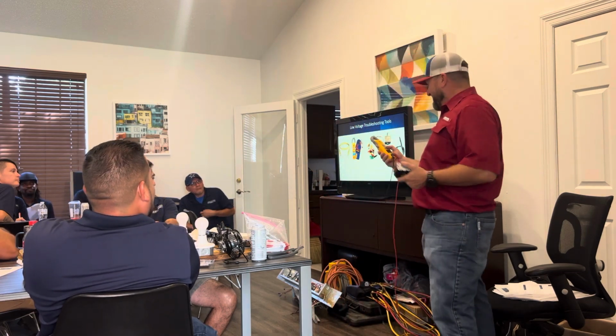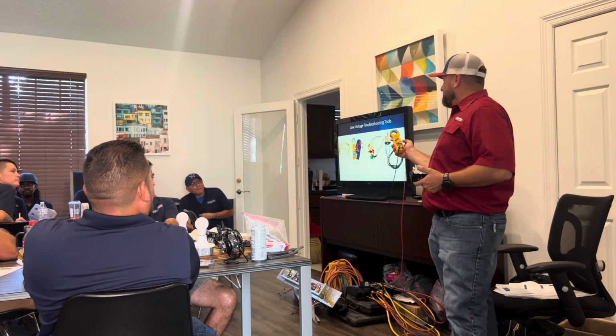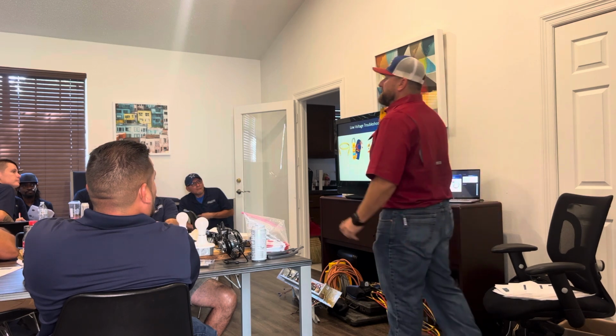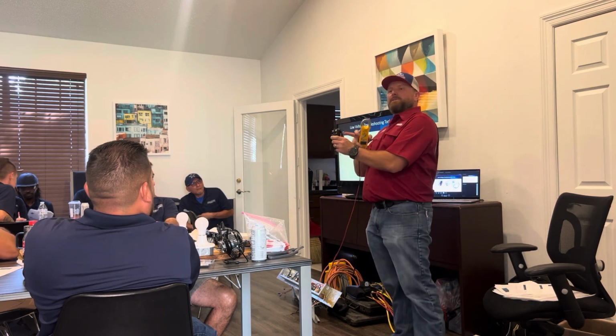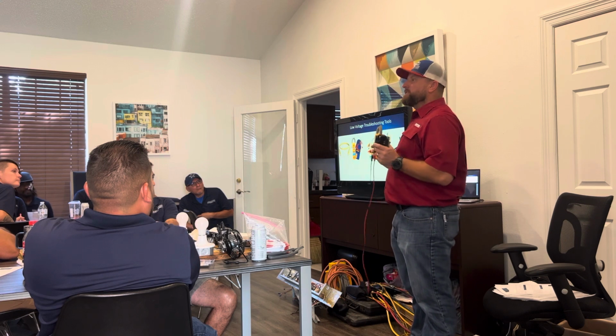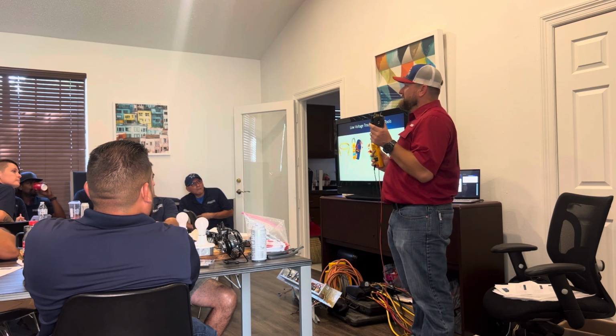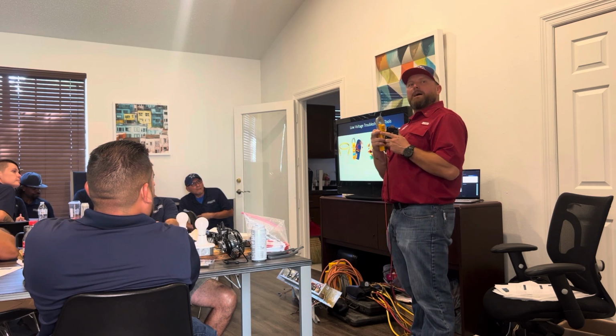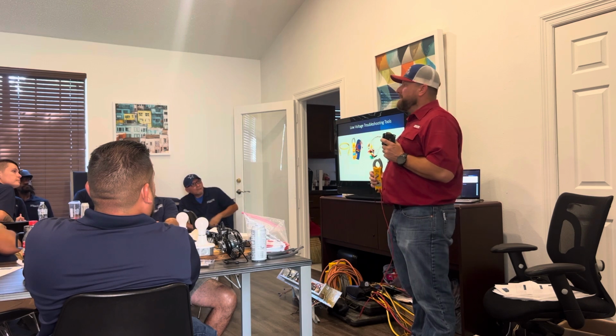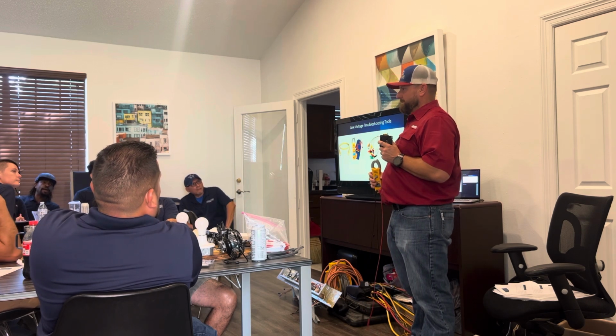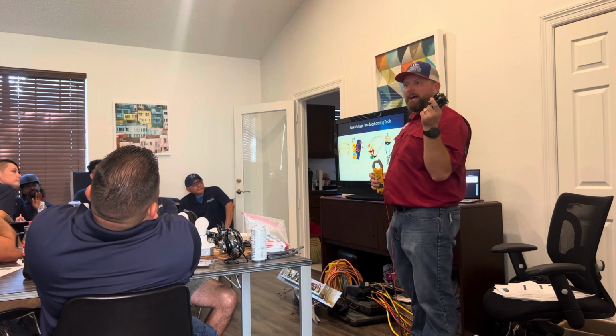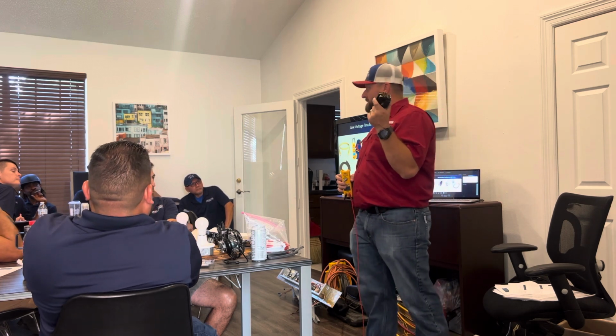Ram, yeah. So you want to check this at volts, VAC, and then just connect on both sides. If you're getting 24 volts to this, and this center is not pulled in, what does that mean? That contactor's bad, more than likely.